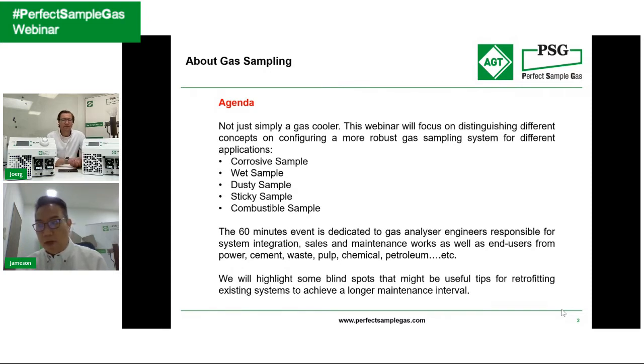You see? So having a reliable constant dew point, I would say, has an impact on the gas analyzer calibration. Yeah. And any gas analyzer calibration needs to have good repeatability, and they like to have good reproducibility of the results. You see? So I think, and this was also very interesting when we put up the poll on our LinkedIn page.